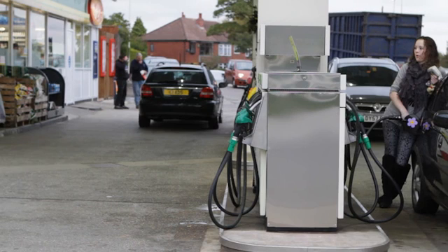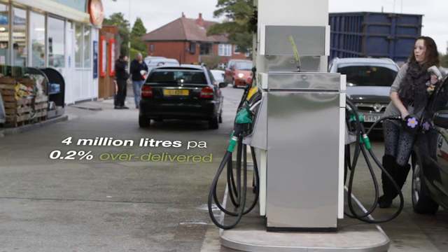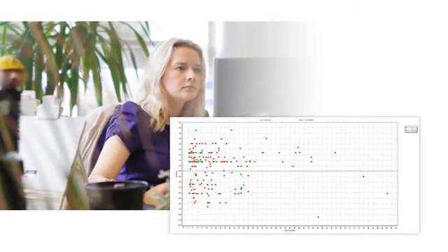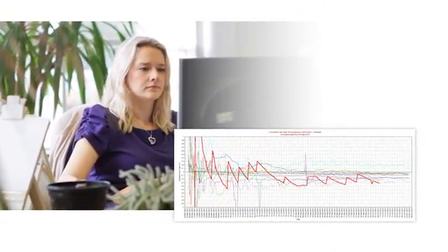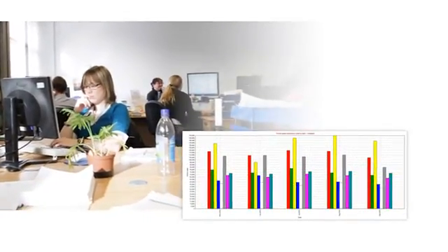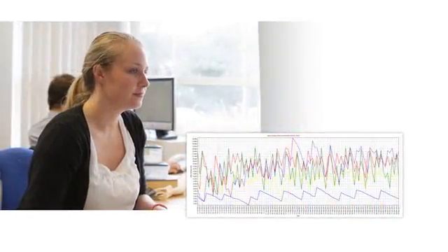And even these smaller losses can be very costly. For example, on a forecourt with annual fuel sales of 4 million litres and dispensers over delivering by just 0.2%, you could lose 8,000 litres. Gradual losses can go unnoticed for a long period of time, and separating out this loss trend from the background noise can be a challenge, particularly where human intervention and tank calibration can distort the figures and hide problems.